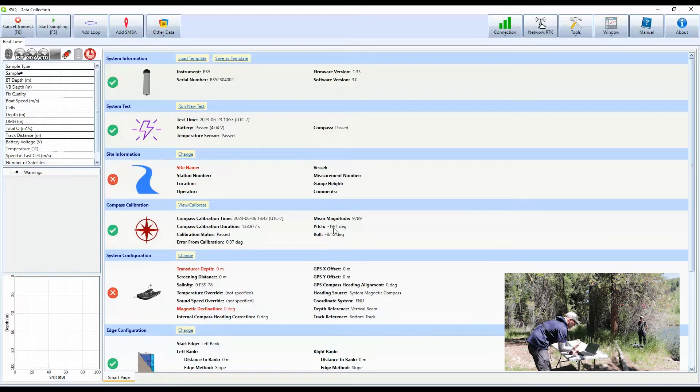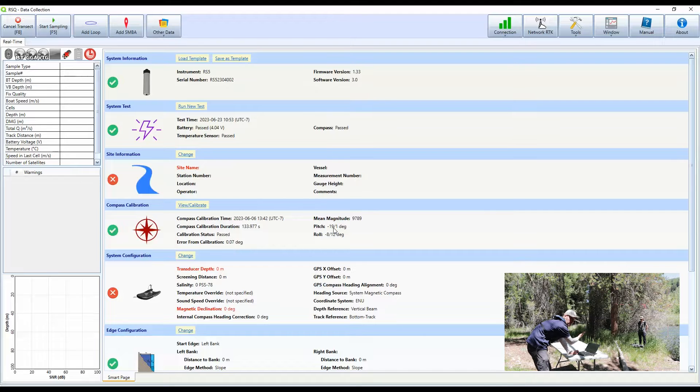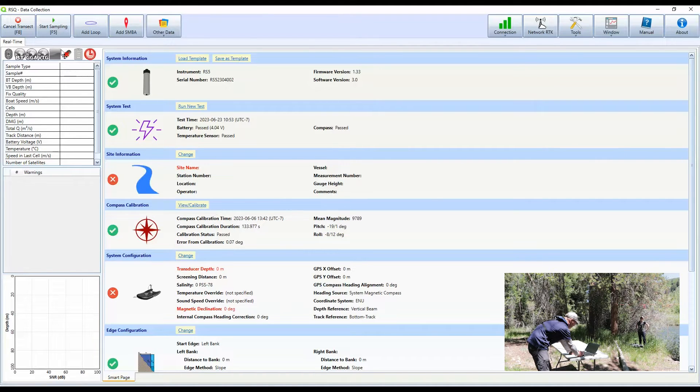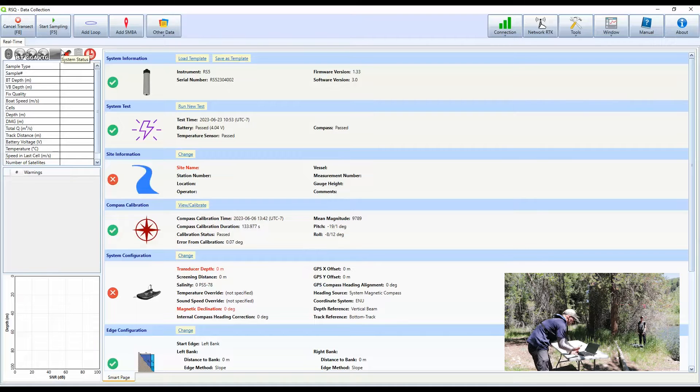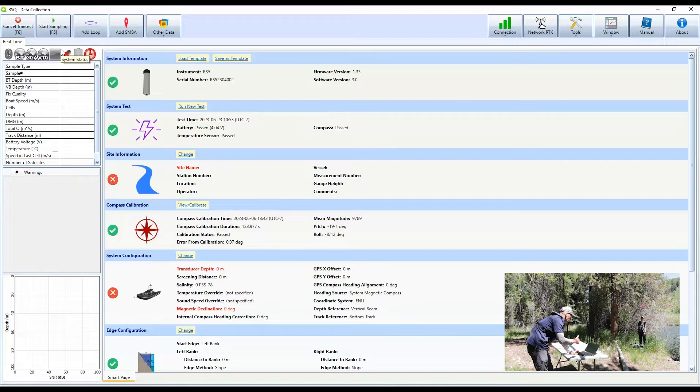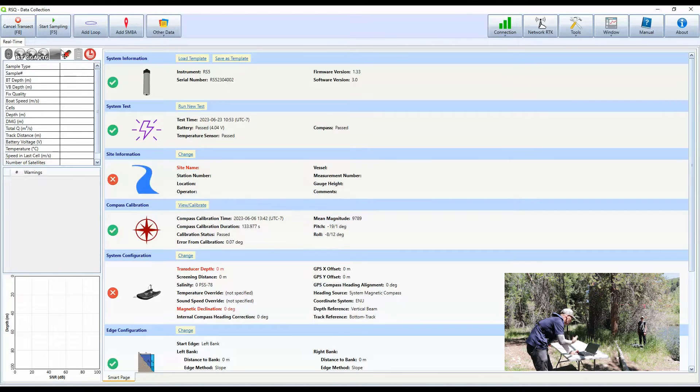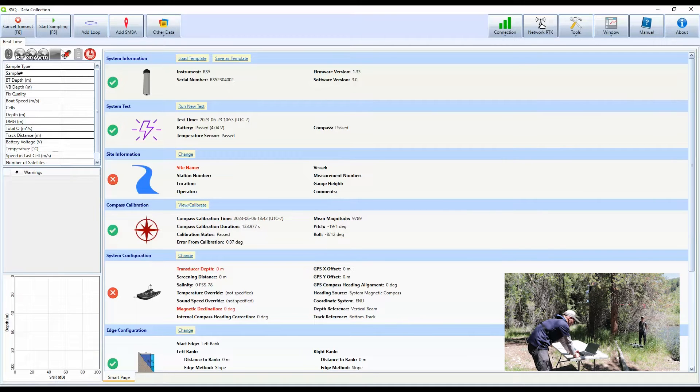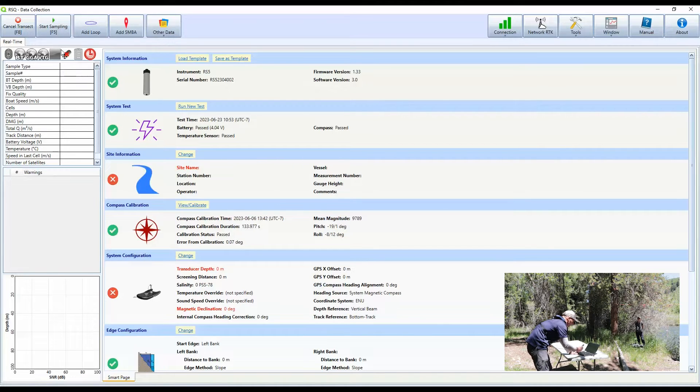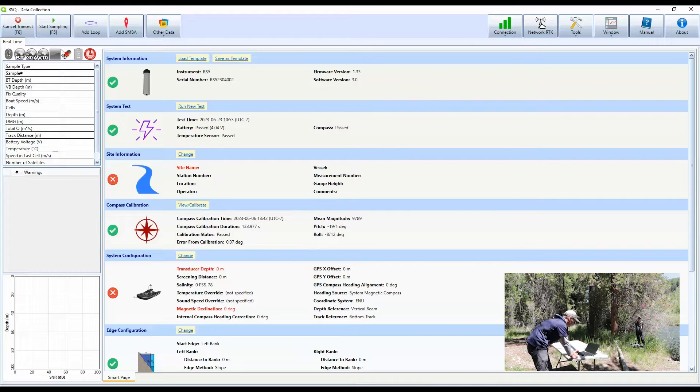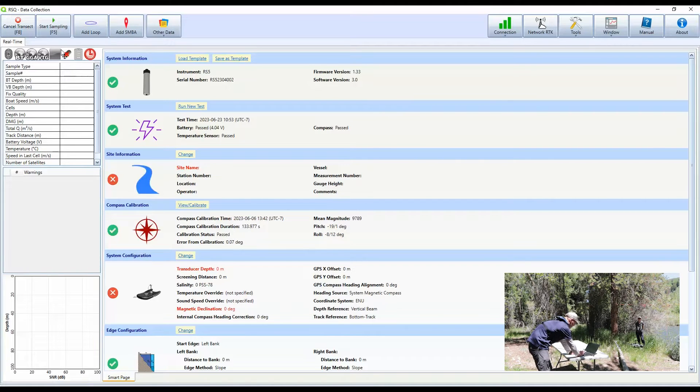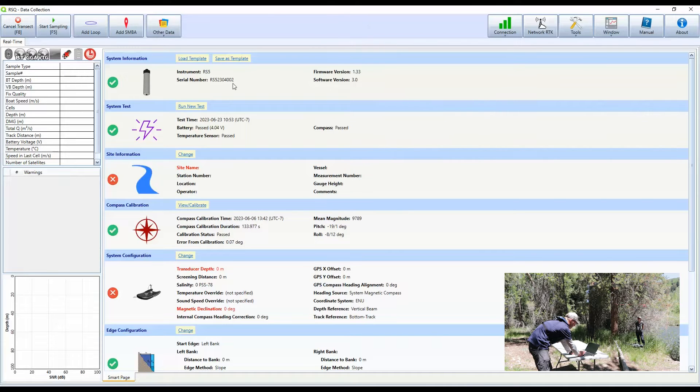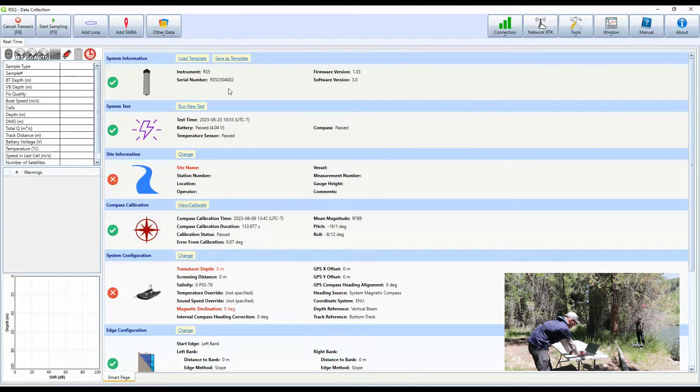Now I'm connected to the RS5 instrument and I'm showing the smart page here in RSQ. The great thing about the smart page is you can just start at the top, work your way to the bottom. And once you have changed any red X's you see here on the left hand side to green check marks, that means you've gone in and updated or configured your system and you're ready for a measurement. The top section is just system information. So that has the firmware version, the software version, and the RS5 serial number.